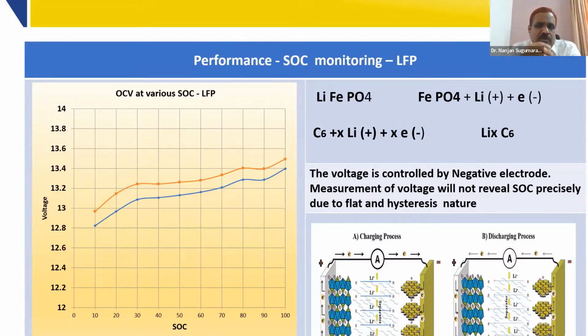LFP is much more safe than NMC - we talked about lead acid, then NMC lithium, and LFP. LFP is more safe, but the problem is in LFP the SOC monitoring is very difficult because the voltage versus SOC curve is very, very flat. Because of this flat curve, it also gives hysteresis - whether you're in the charge state, it gives one voltage, in discharge state it gives another voltage. So this is very, very difficult to predict SOC of an LFP battery.